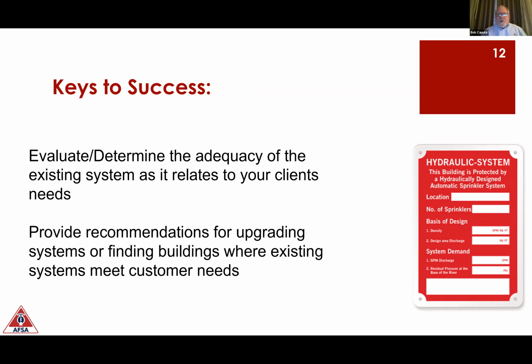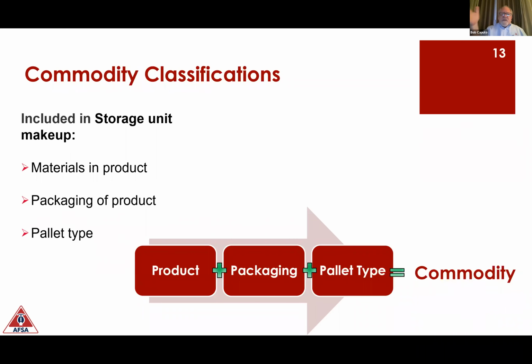Also, in some cases, we require in-rack sprinklers for those large storage facilities with pallet racks that go pretty high. So in those cases, the in-rack system is going to be separate from the piping system at the ceiling. So you will have multiple risers or multiple systems within each building, and that's very, very common. So again, my fire sprinkler system is going to be based on this commodity classification, which includes the product itself, plus the packaging, plus the pallet type. The fire sprinkler system designer is going to take that commodity classification and then evaluate the storage method and the storage height and the building height and come up with a prescriptive based design for the criteria of that particular client within that particular building based upon the NFPA 13 standard.